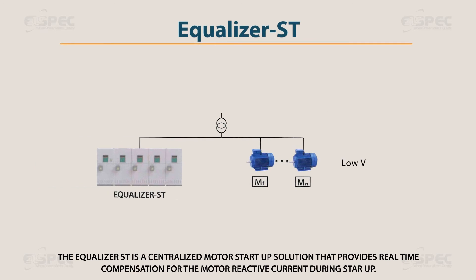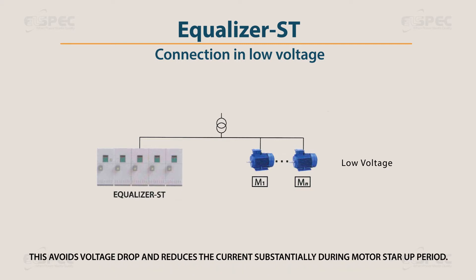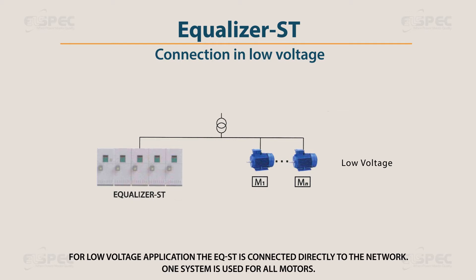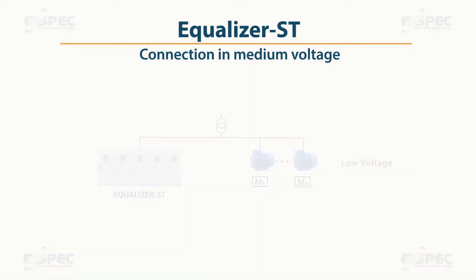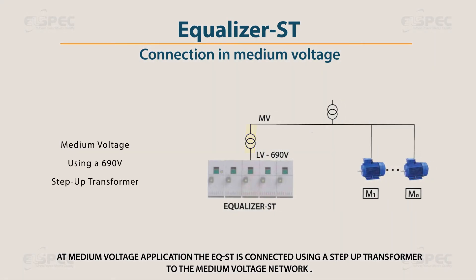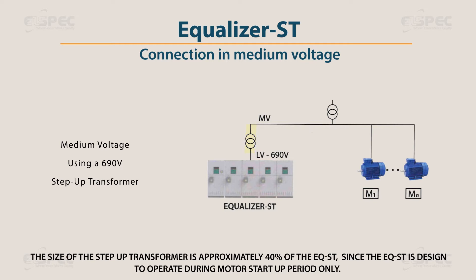The Equalizer ST is a centralized motor startup solution that provides real-time compensation for the motor reactive current during startup. This avoids voltage drop and reduces current substantially during the motor startup period. For low voltage applications, the EQST is connected directly to the network, with one system used for all motors. At medium voltage applications, the EQST is connected using a step-up transformer to the medium voltage network. The step-up transformer is approximately 40% of the EQST size, since the EQST is designed to operate during motor startup period only.